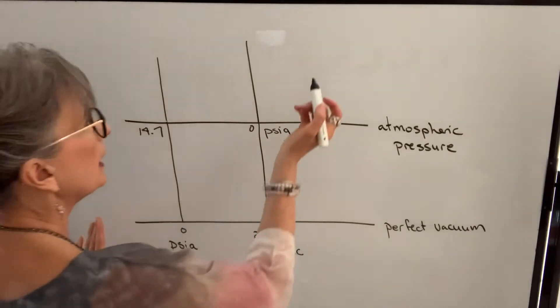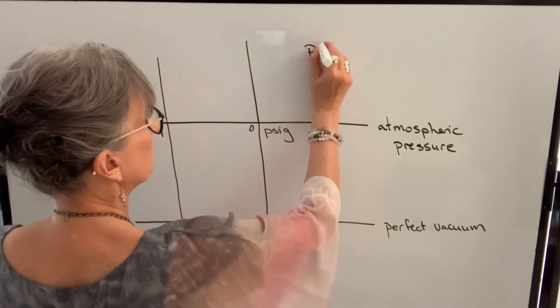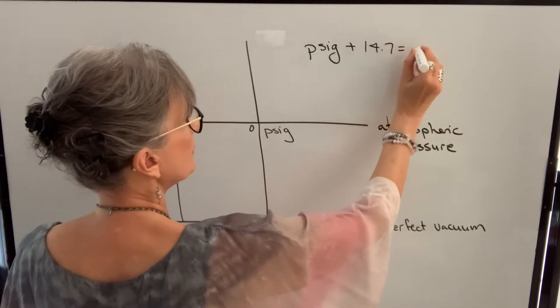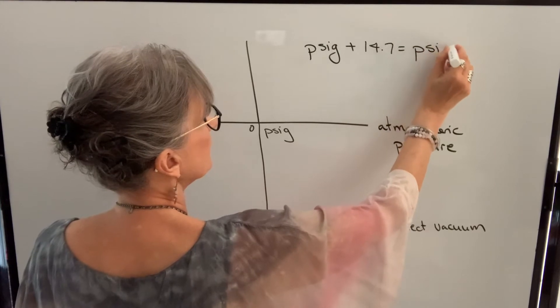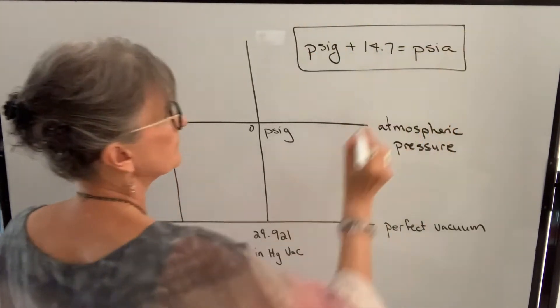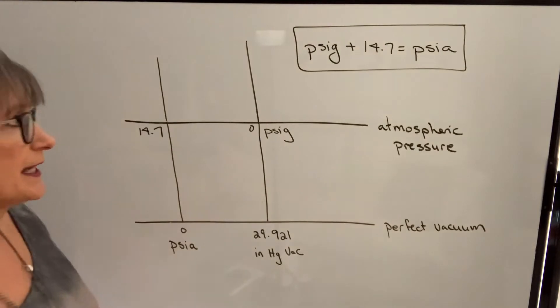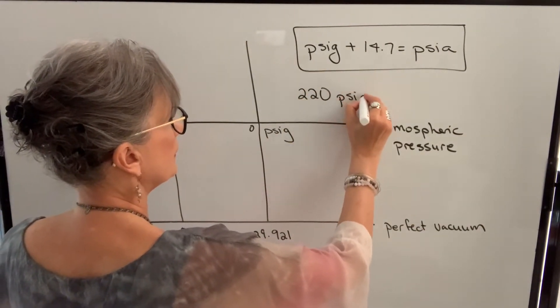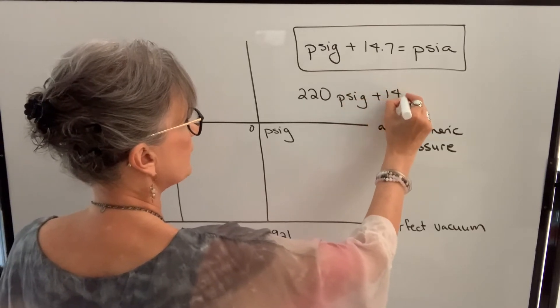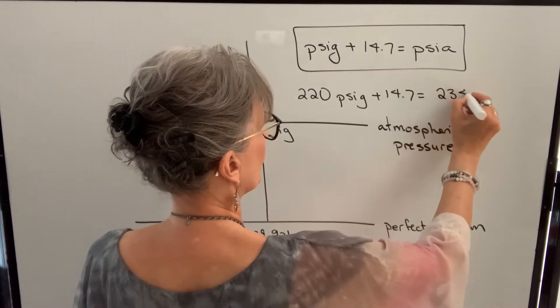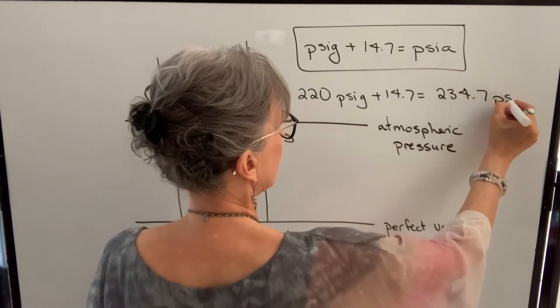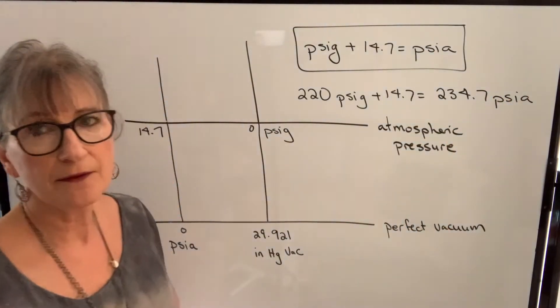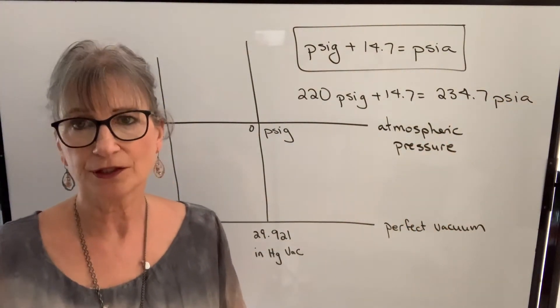PSIA will always be 14.7 greater than PSIG. So if you're given a pressure in PSIG on your gauge, you add 14.7 to get the pressure in absolute. For example, if I had 220 PSIG, I would add 14.7 and get 234.7 PSIA. Once I've changed my gauge pressure to absolute, I can use it in my formula for calculating compression ratio.